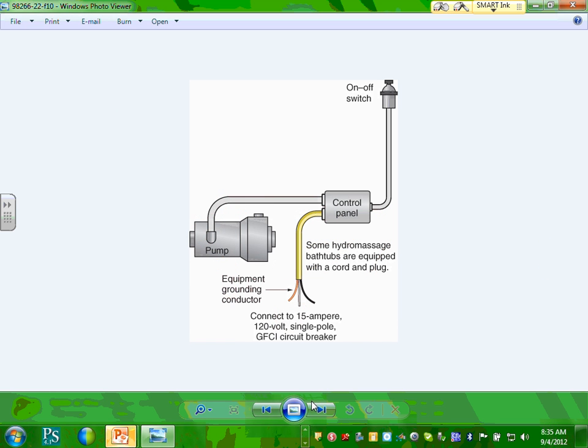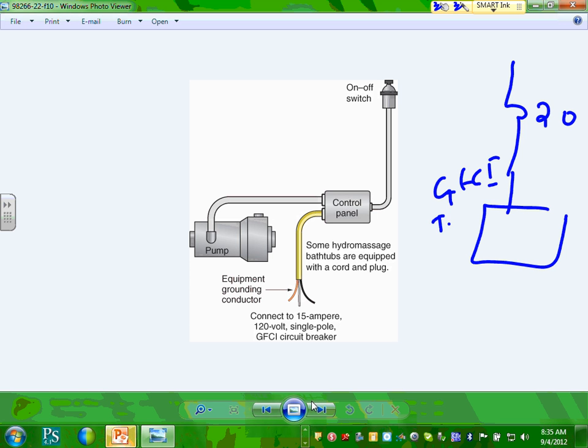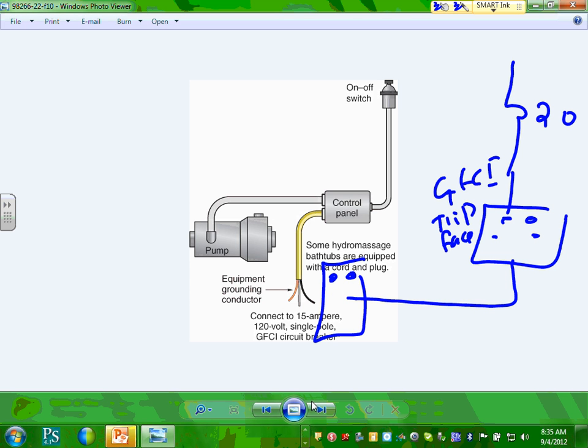Hydromassage bathtub, guys. It typically looks like this. You're going to have a 20 amp circuit here, a GFCI circuit, which just has the GFCI in it. And it comes over here to a receptacle, tied to a receptacle, and these wires will be plugged into the receptacle. That's typically exactly what you're doing.